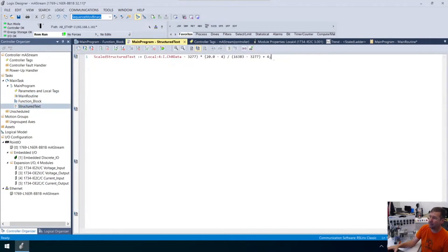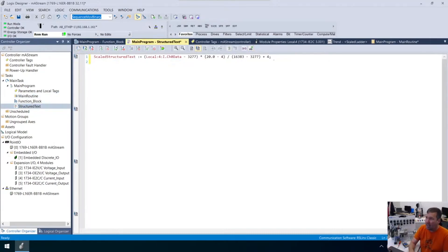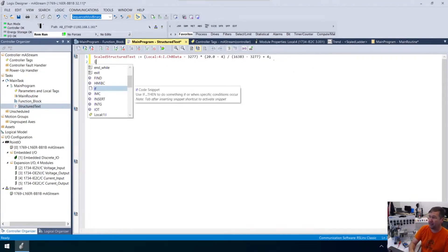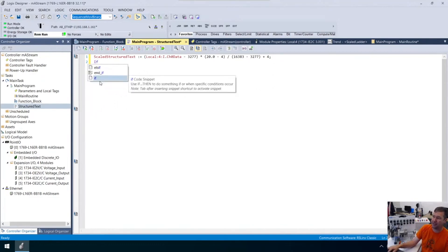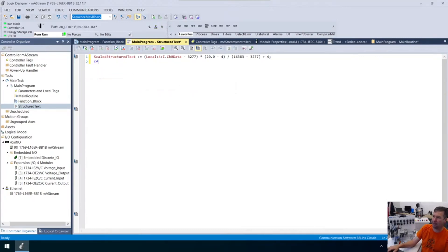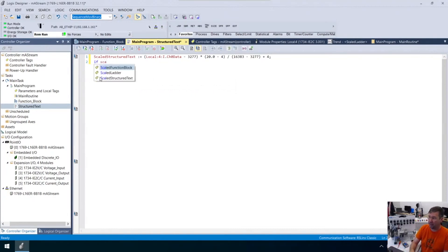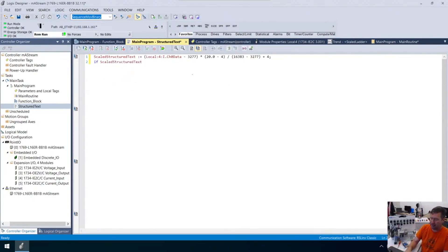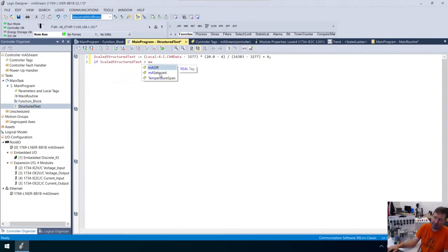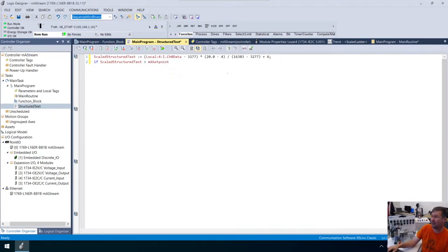Let's say if the value is less than 12, or the ladder is less than 14, and the motor is running, or our pump is running, or our heater is running, whatever, then turn on the output. We can type that out in structured text. So if we go over here and we edit this, we're going to go to the next line, and we're going to type if. And you start typing, and all your instructions are going to come up. So if you're not sure, there it is, if. And we can even mouse over it, and okay, if then, that's what we're doing. So we're going to double click there. And so the first thing was that our scaled, in this case, we're going to use the scaled structured text, is greater than our MA. And remember, this was cool. Even though it's structured text, I would always use the drop-downs because I'm not a great typer, but our milliamp set point. So there's our first condition.